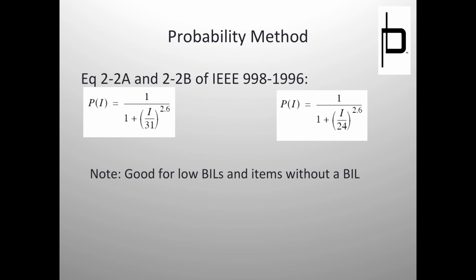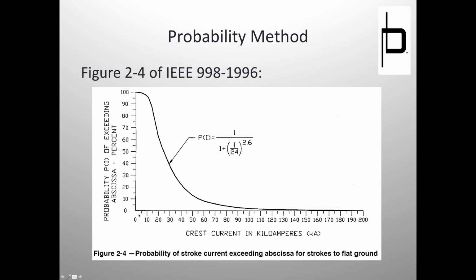I actually prefer using this because if you think about it, if we use 2 kA, 2 kA accounts for some 99.5. It's going to be a big number. Right. Are we being too conservative, too picky here? That's possibly. So I always do what the client tells us to do, and it's unique to their situation, but I always recommend not going below 99%.